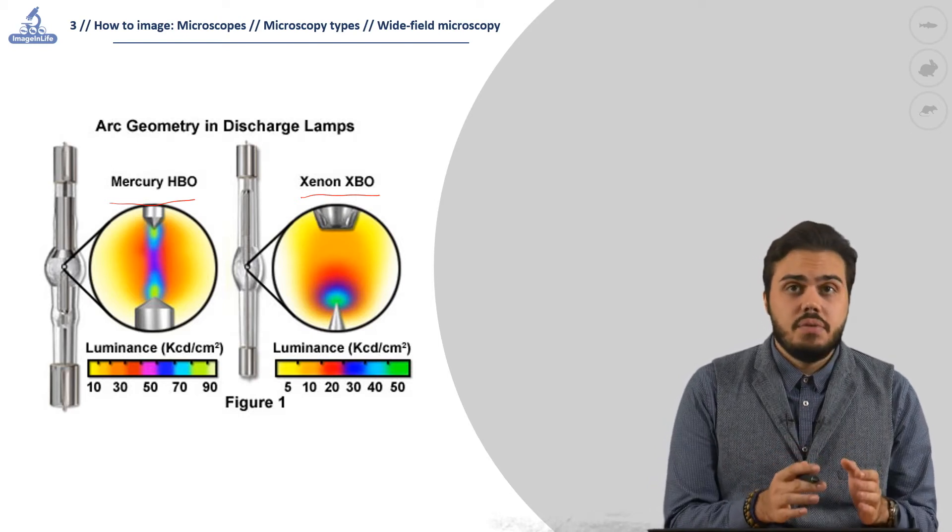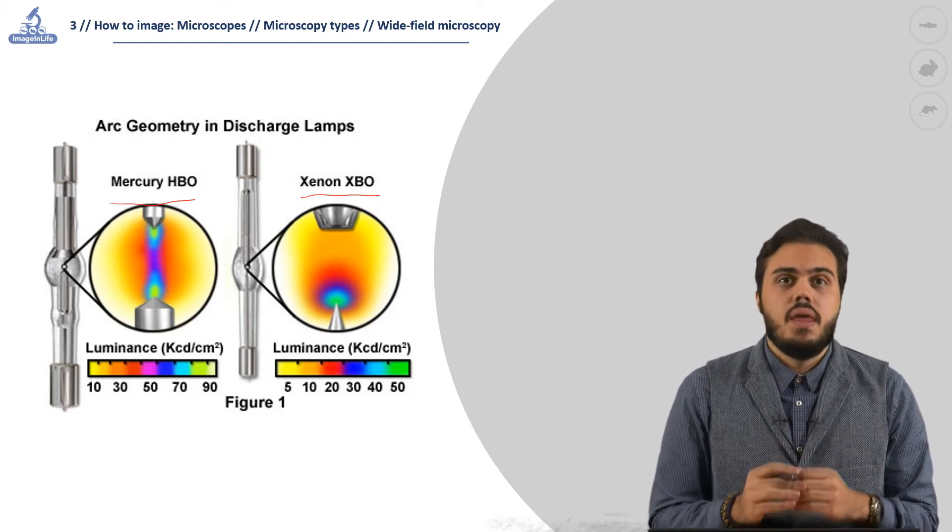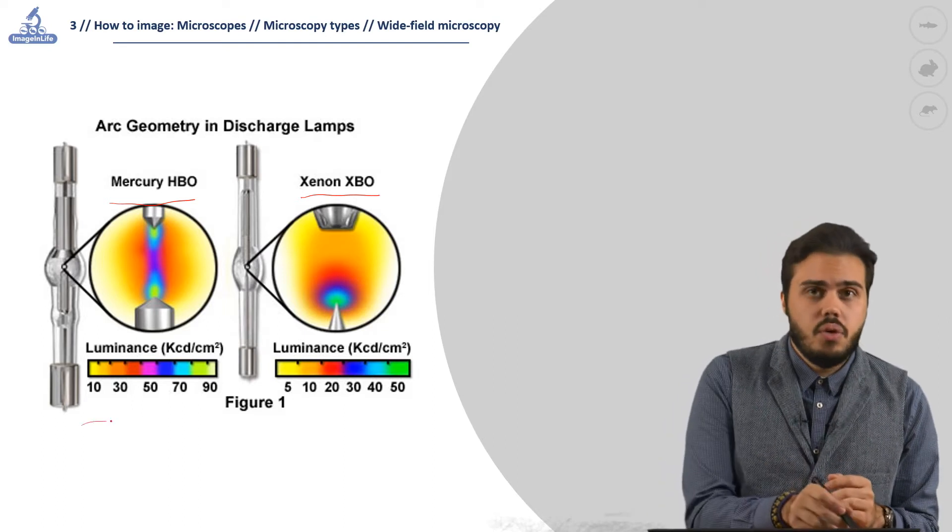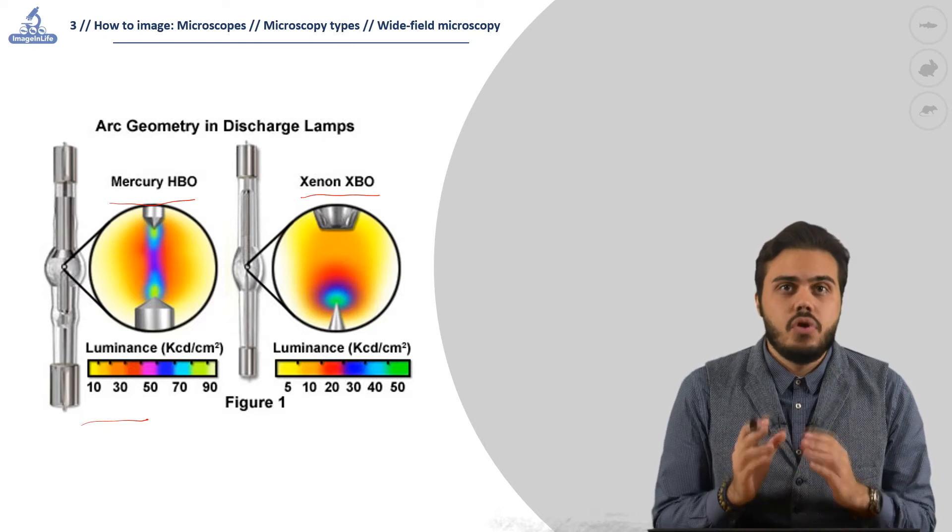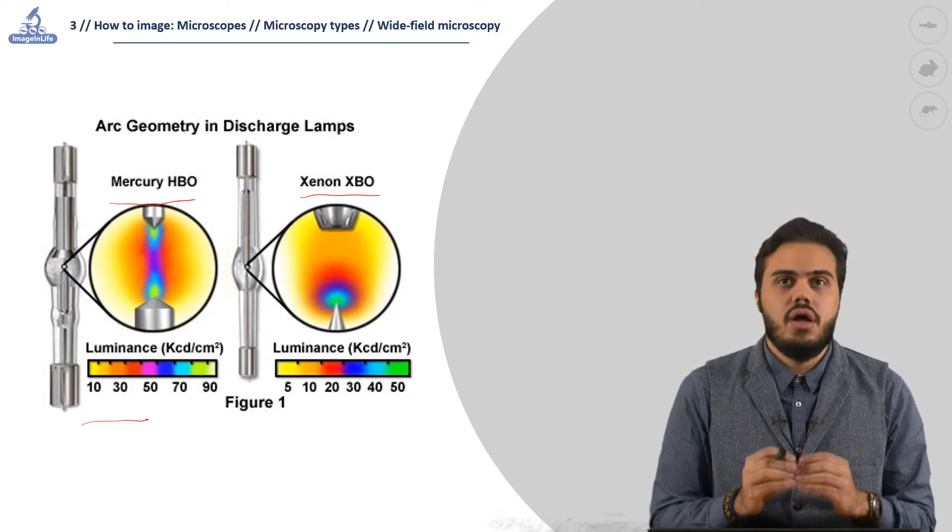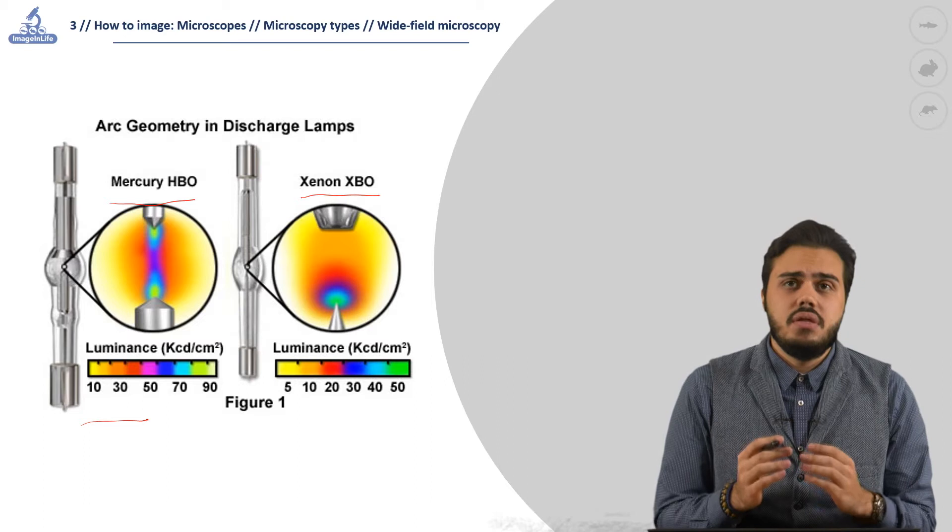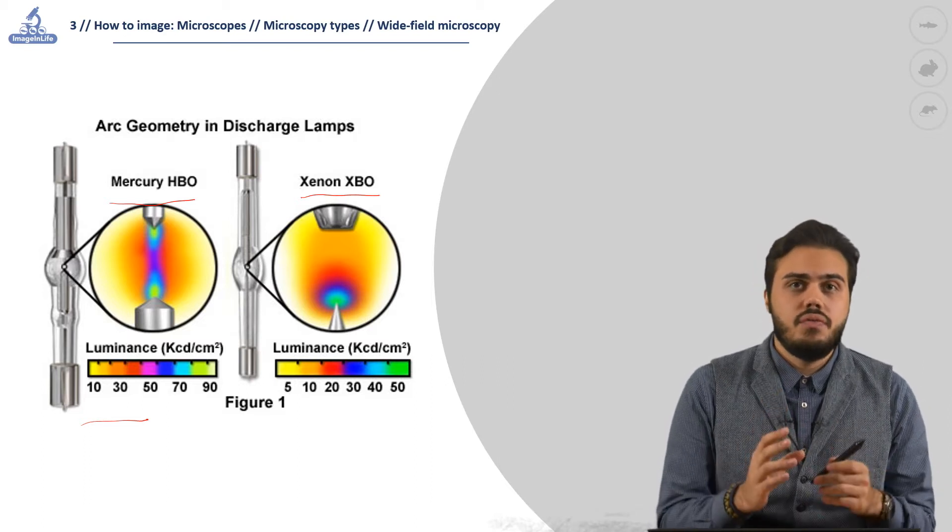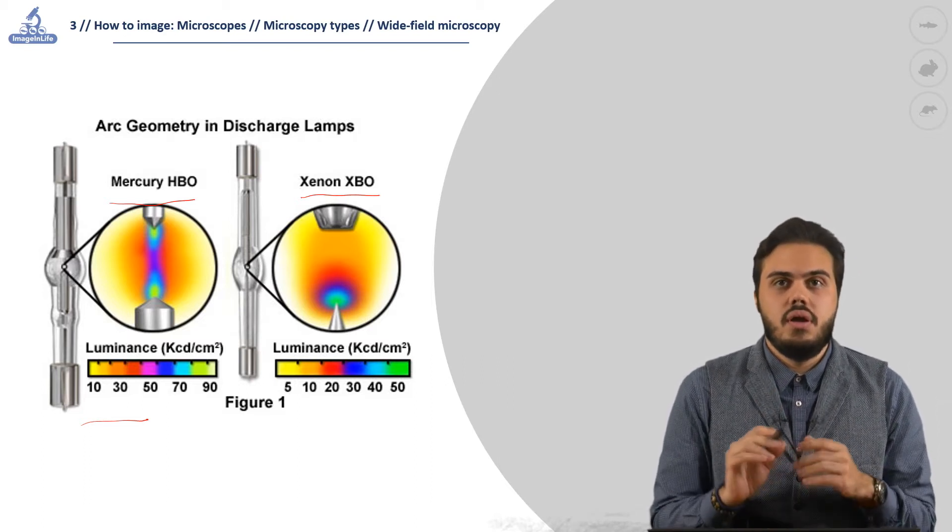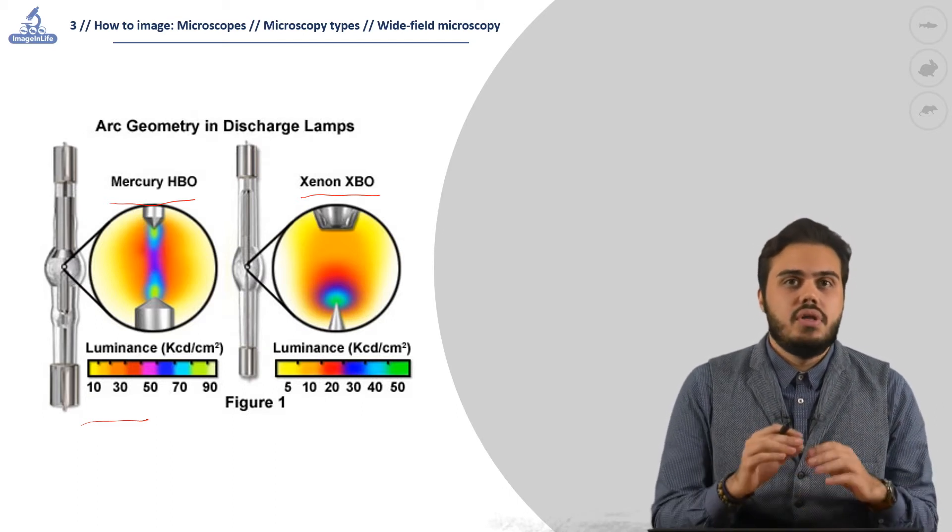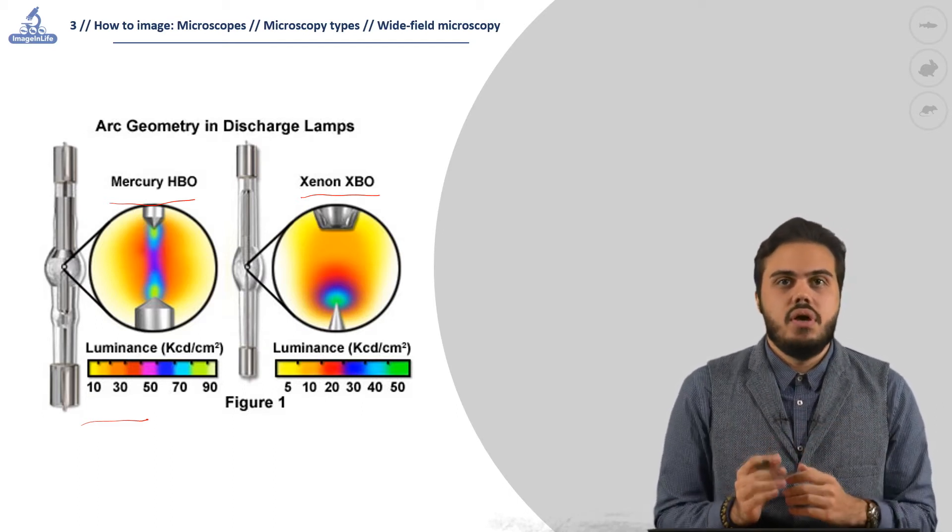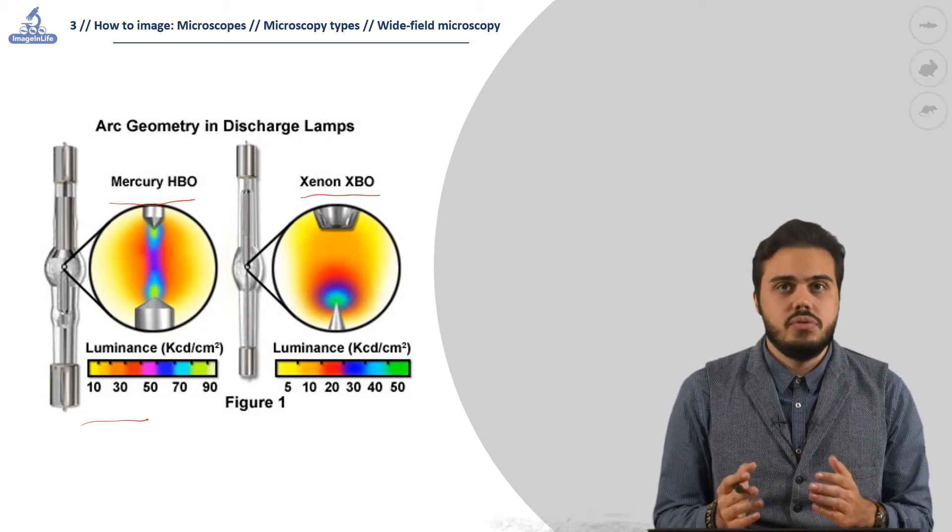The arc lamps have a reduced lifespan—300 hours for the mercury one and 600 hours for xenon—and this lifespan is greatly reduced by switching on and off the lamp. This means that the user has to carefully keep track of the usage of the lamp. The lamps over the lifespan have the risk of exploding and need to be disposed carefully with special procedures.